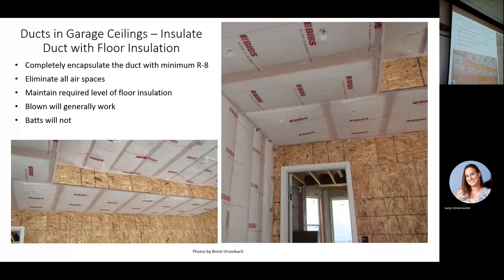We've looked at this, and this builder that built this house, this is what he's started doing on all of his rooms over his garages. And he was getting lots of complaints with his rooms over his garages. The air wasn't warm coming out of the registers because the duct was in a space that was semi-conditioned, maybe not fully conditioned. It was cooler coming out in the winter time. It was warmer coming out in the summertime. And so he started doing this for his systems, his garage ceilings.